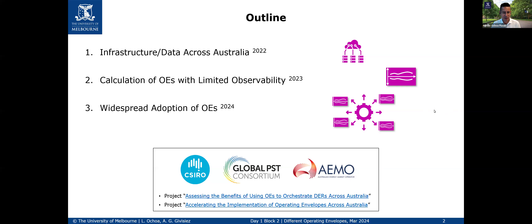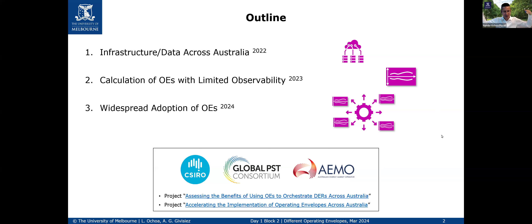Everything I presented in block one was related to the low-voltage transformer and corresponding customers or the SWER network. In reality, if multiple neighborhoods are using operating envelopes, they affect everyone because they're connected to the same electrical network — assuming they're part of the same high-voltage, medium-voltage feeder. Those effects of people using operating envelopes will affect the voltages of others. So calculations are not limited to the low-voltage; they have to consider the high-voltage — 22 kV, also called medium voltage internationally.